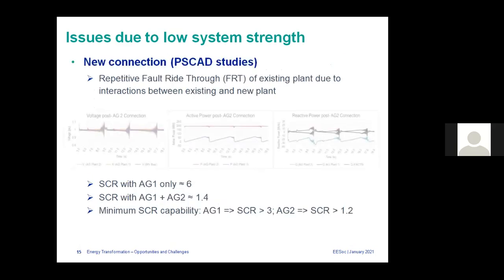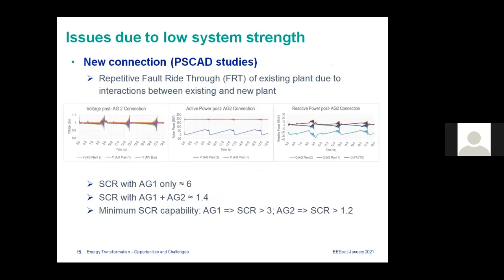And there is another one, a similar case at the same location. Again, these are PSCAD studies, because we had another wind farm coming to the same location. What we found is that under system normal, with only the first plant, we have an SCR of about 5 or 6. But when you add the second plant, SCR drops to about 1.4, because you have to add the megawatts of the two plants and you have the same fault level. The short circuit ratio drops significantly. The existing plant's inverter technology is very old, so they say they can't operate in a stable way if the SCR is less than about 3. So we can expect a problem if it drops to 1.4.